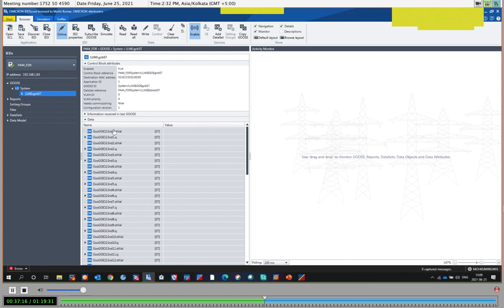So here you can see indication one, general input output. This is very bad implementation. This is edition one, kind of old implementation. Nowadays we can implement it in much better way. You can use PTRC and other kind of namings instead of using GGIO. So I do not recommend to use GGIO. Then it has up to 32. Yeah. We can verify 32 status values and with the quality, and we can just dig down what is meant by the quality of these status values.